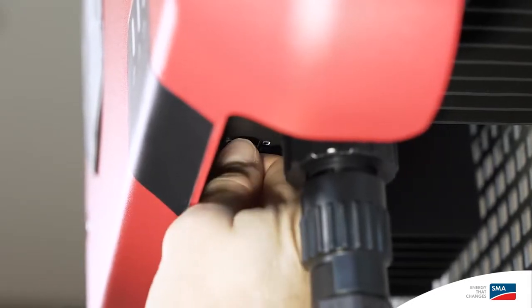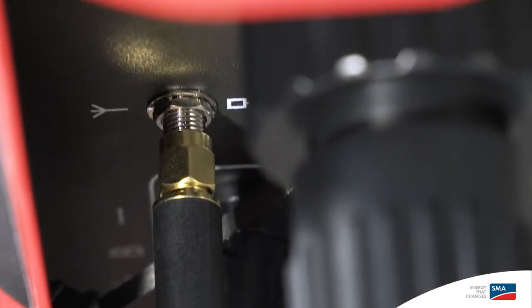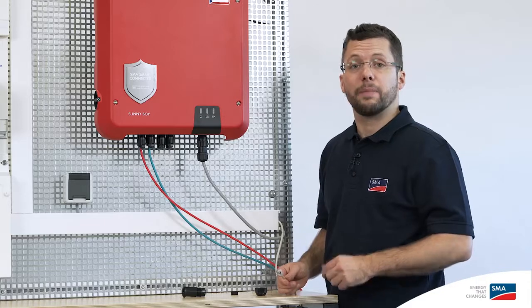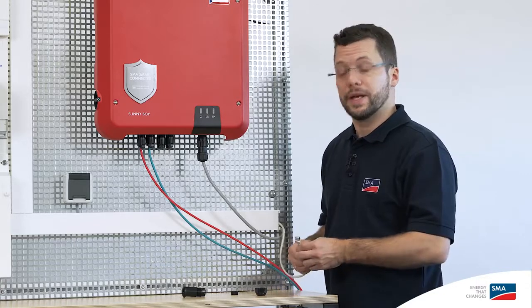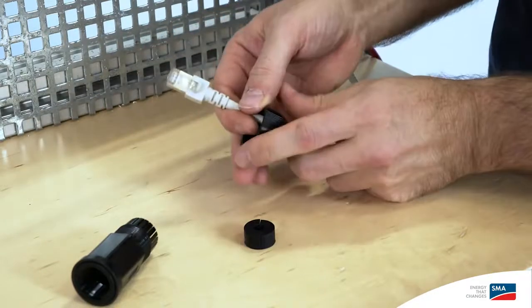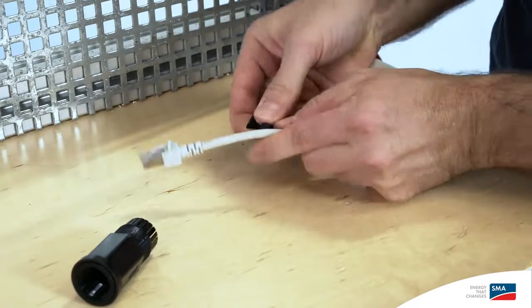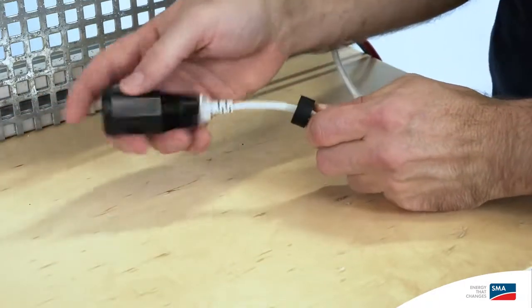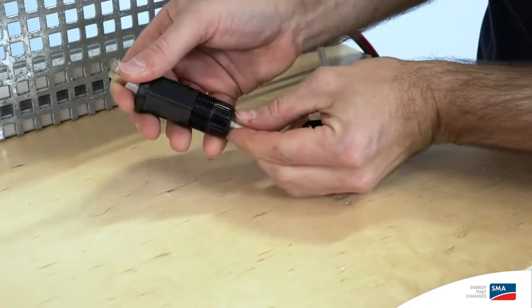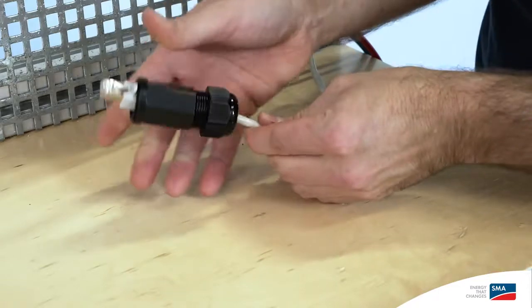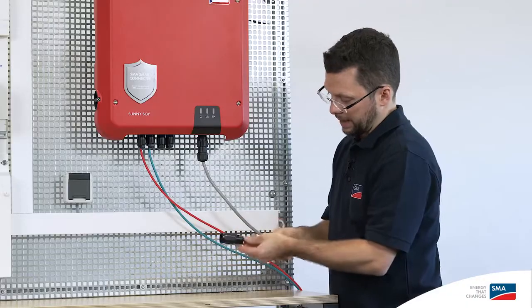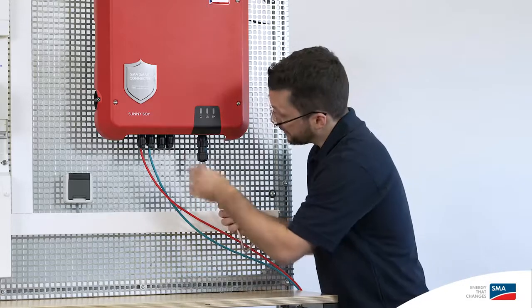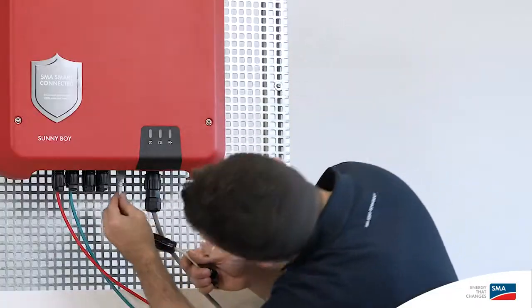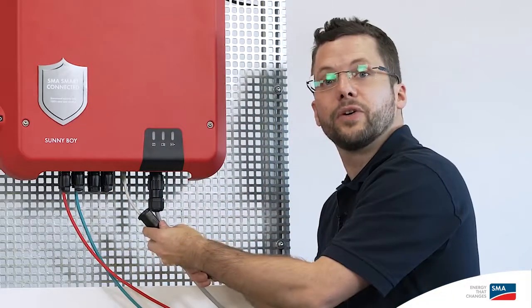The easiest way to establish a communication option with the inverter is to unscrew the red cap and then screw on the WLAN antenna supplied. To connect the inverter to the energy meter or Sunny Portal using an Ethernet cable, it's important to first equip the Ethernet cable with a swivel nut. Then attach the rubber sealing ring, and then place the threaded sleeve over the Ethernet cable. It's best to fit the rubber seal at the end of the threaded sleeve. Now we can insert the Ethernet cable directly into the Ethernet jack on the inverter. Next, slide on and tighten the threaded sleeve.